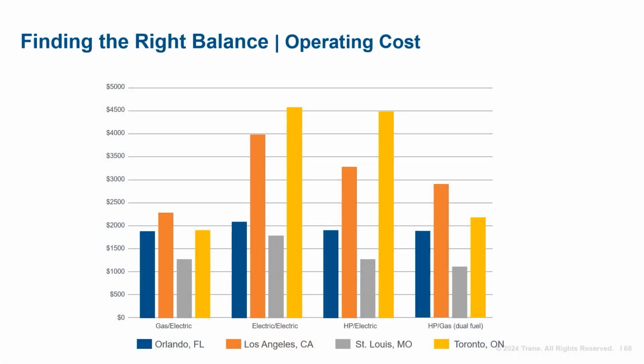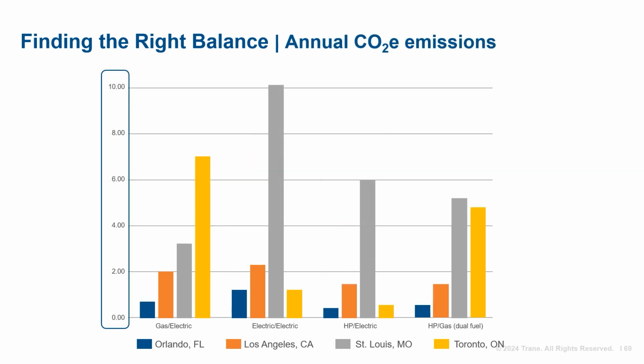As we look at the 4 cities, it is apparent that one size or system type does not fit all, and the proper unit selection is based on several factors. One being the owner's goals or area of focus. Is the owner looking to save as much operating energy as possible? Here we see an annual operating cost comparison for the 4 cities we analyzed for the 4 rooftop system configurations that we compared. Or does the desire to electrify and/or decarbonize overrule the need for the lower operating costs?